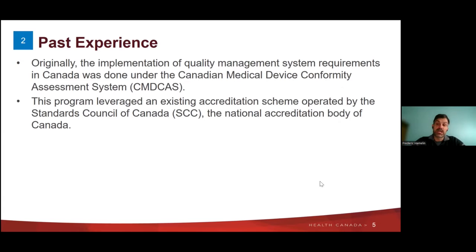And that's when we first brought in quality management requirements into our regulatory framework. This didn't specifically come into force until 2003 for a number of different factors. When it did become applied, it was under a scheme we call the Canadian Medical Device Conformity Assessment System, or what we would just refer to as CMDCAS. And again, this was a requirement for a 13485 certification issued by bodies that are recognized by the government.